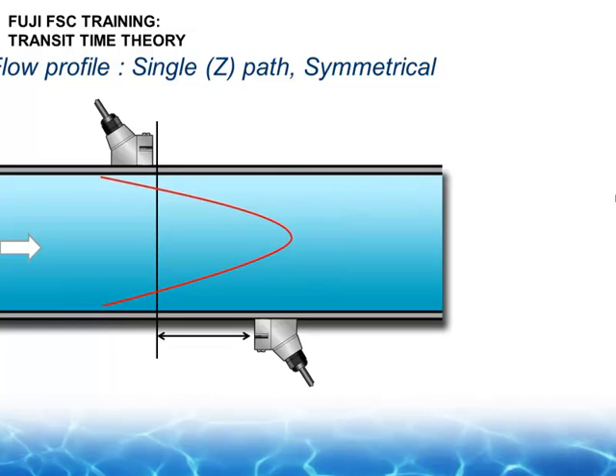The Fuji transit-time flow meter is destined and its objective to be a 1% type of technology. That's based upon the math, and the math basically dictates that this transducer will be located here and this transducer will be located here, and the time it will take to get from this transducer is predetermined mathematically. That's all known in advance. So if the pipe was just full of liquid with no moving flow, these two sensors would be saying hello back and forth there, everything's perfect.